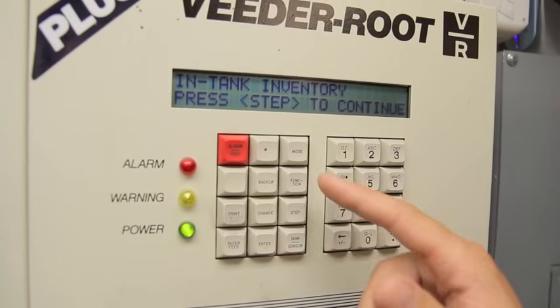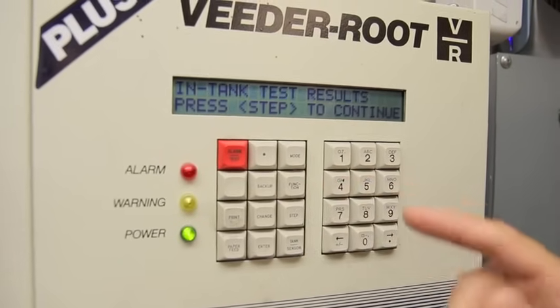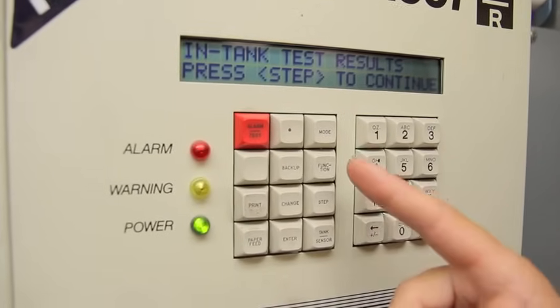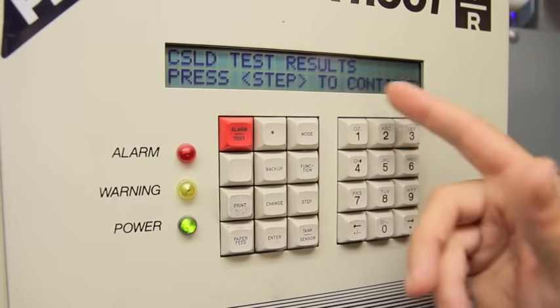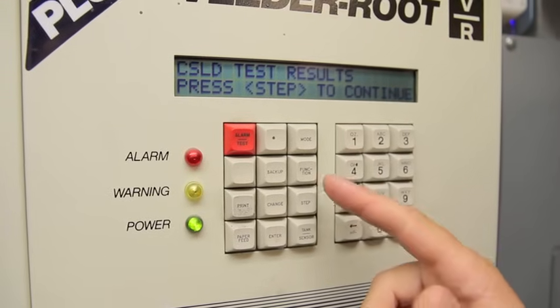This can give us in-tank inventory. This can give us shift inventory from the last shift. This can do an in-tank test result reading so we can see if the tank passed the leak test. This particular monitor is set up with CSLD. If you're a Veeder-Root owner and it says CSLD, then you are doing continuous statistical leak detection, so you can get test results that way.